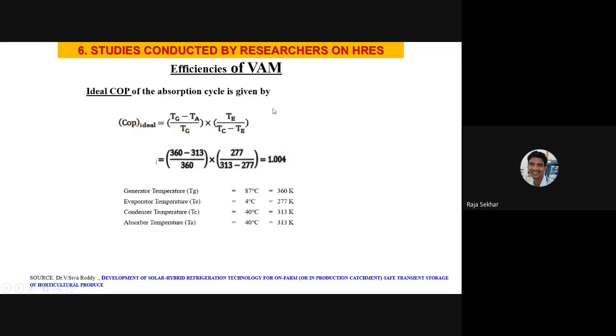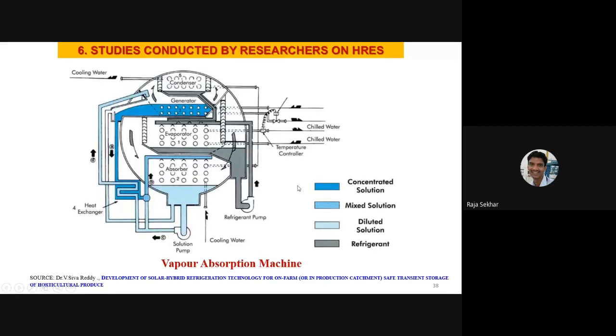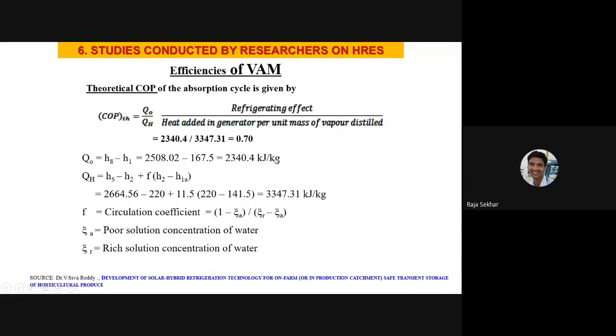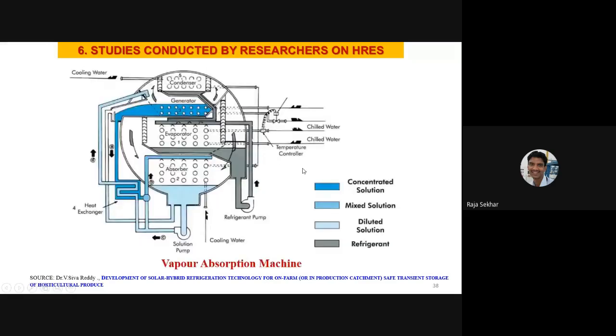Coming to the LiBr-based theoretical effectiveness, our ideal efficiency is 1.004 for these operating conditions. However, for the conditions available at that location, they are able to get a COP of around 0.7, which is somewhat closer to the ideal COP. You can increase this COP based on the conditions that you maintain.